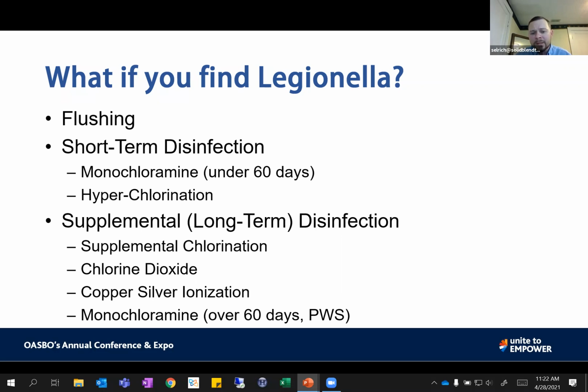For problematic systems that have ongoing Legionella positive results, there are some long-term options that you can put in place: supplemental chlorination, chlorine dioxide, copper, silver, and monochloramine. We typically go with the monochloramine. It's been very effective long-term and short-term for Legionella control.